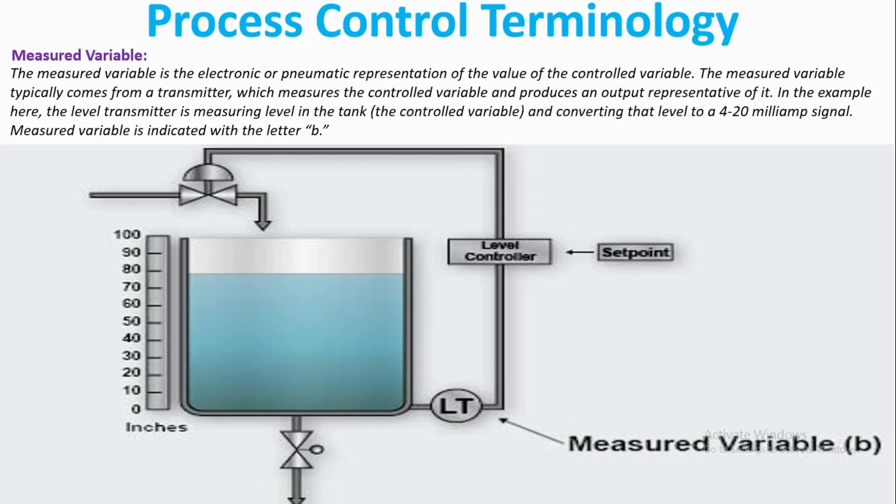In the example here, the level transmitter is measuring level in the tank, the controlled variable, and converting that level to a 4 to 20 milliamp signal. Measured variable is indicated with the letter B.